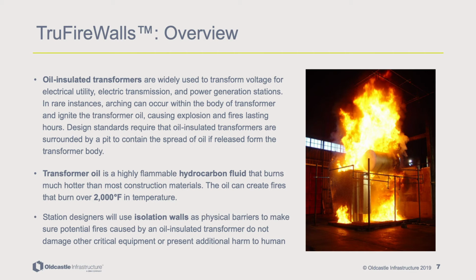Transformer oil can create fires that burn over 2,000 degrees Fahrenheit in temperature. Station designers will use isolation walls as physical barriers to make sure potential fires caused by an oil-insulated transformer do not damage other critical equipment or present additional harm to human life.